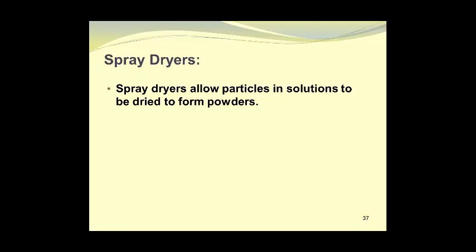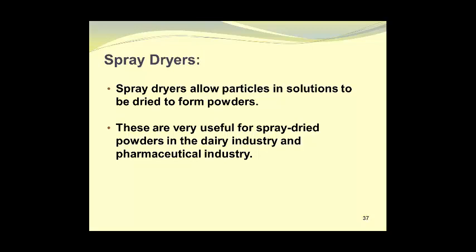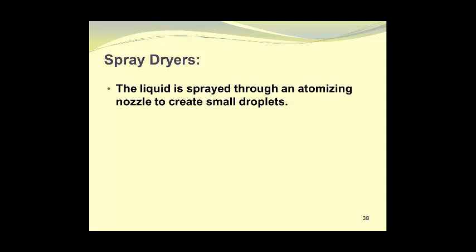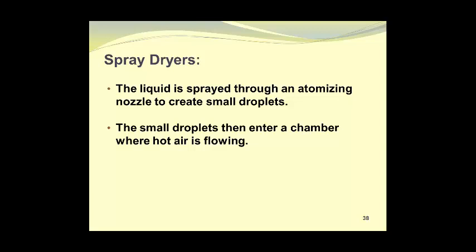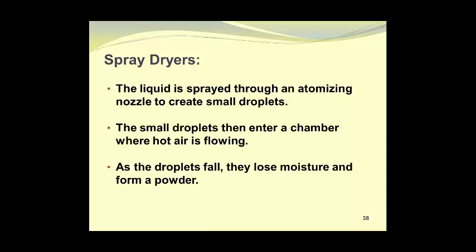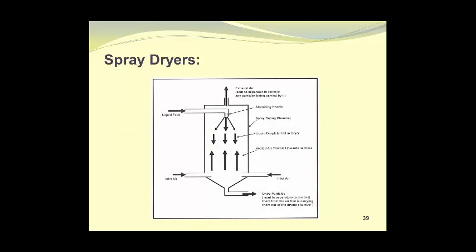Spray dryers allow particles in solution to be dried and to form powders. These are very useful for spray dried powders in the dairy industry as well as in the pharmaceutical industry. The liquid is sprayed through an atomizing nozzle to create small droplets. The small droplets then enter a chamber where hot air is flowing. As the droplets fall, they lose moisture and form a powder, which is then collected. Here is a schematic diagram of a spray dryer. The liquid feed enters from the top left, goes through an atomizing nozzle, and the spray travels downwards as liquid droplets falling in the dryer. The heated air traveling upwards removes the moisture and the particles fall to the bottom. They are a real workhorse in the pharmaceutical and dairy industry.